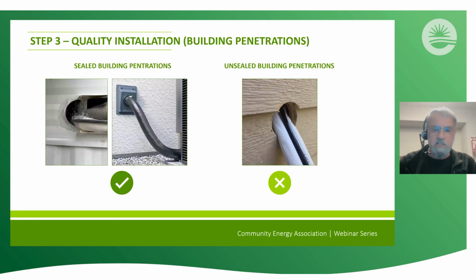Building penetrations. This goes unnoticed quite often. It's amazing how many times we've seen this. There's a good way and a not good way to do it. Now on the left, you'll see nicely sealed. It has a box that is intended for those refrigerant lines, your wiring, everything to go through, nicely sealed in an aesthetically pleasing manner. But more important than anything else is it's nicely sealed. That really matters a lot, as opposed to on the right-hand side there, where it's not sealed.